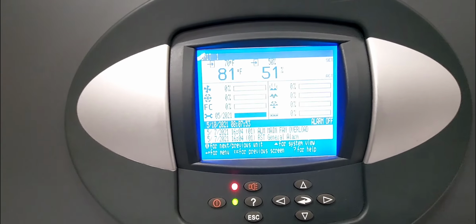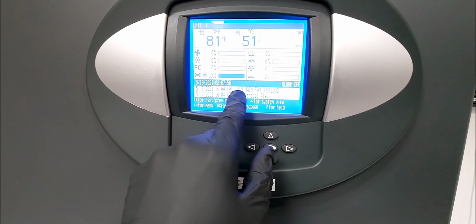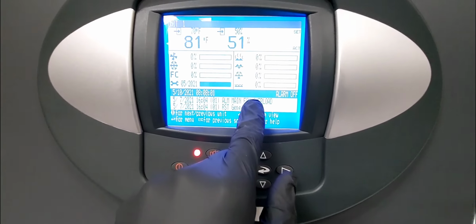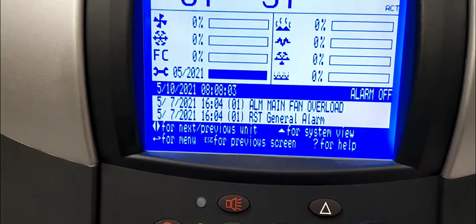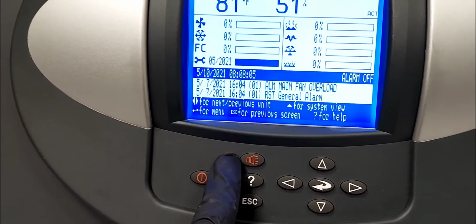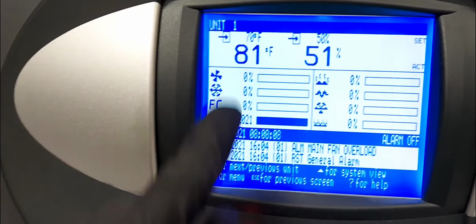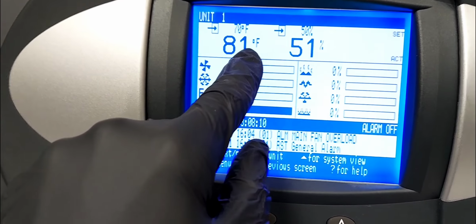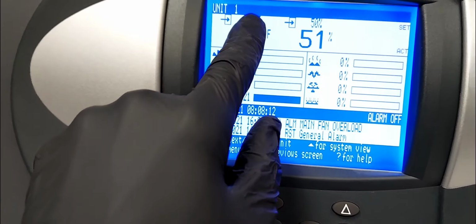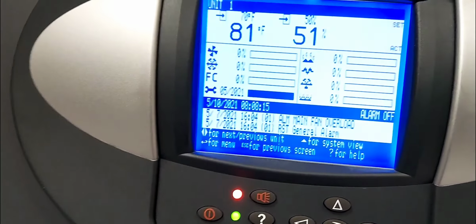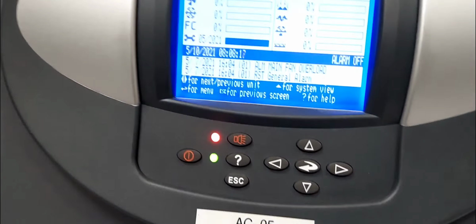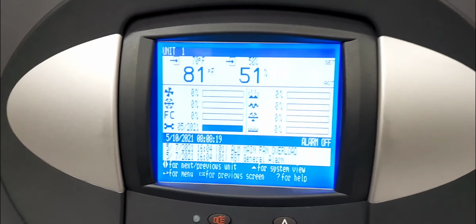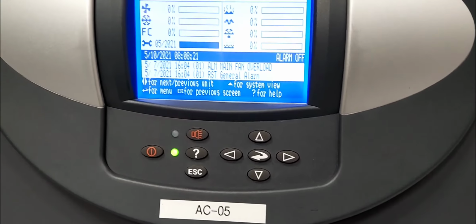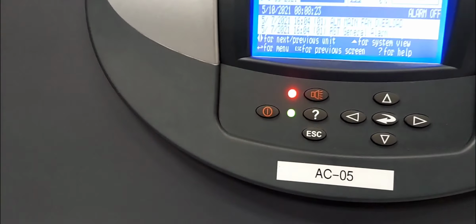Alright, so here is the current alarm. It says the current alarm is main fan overload. Alright, so clearly you can see the alarm light is red, it's flashing. The temperature is high, 81 degrees. The set point is currently 70 degrees. So definitely there's a problem. Alright, so stay tuned, go with me through this diagnostics, and we're going to be doing it together.